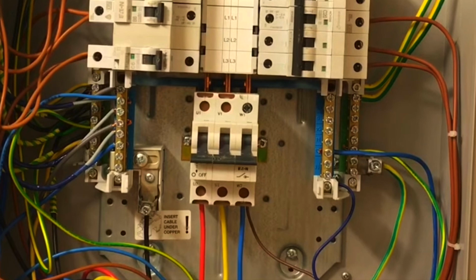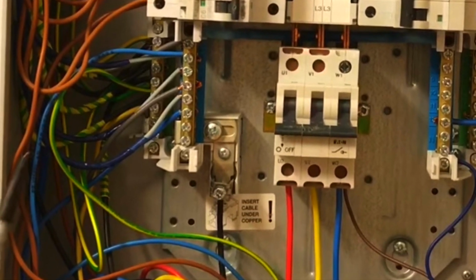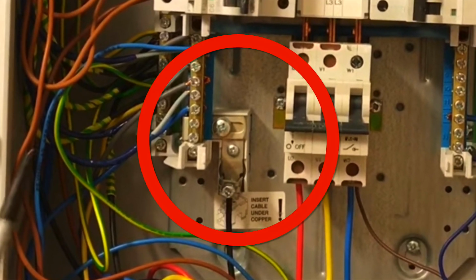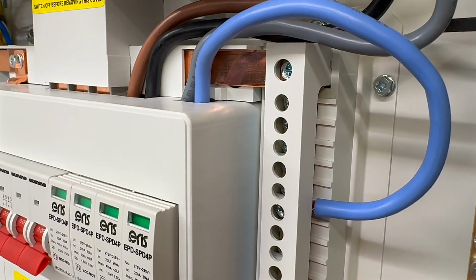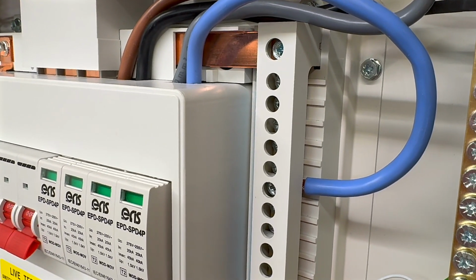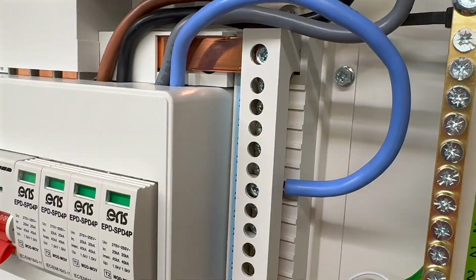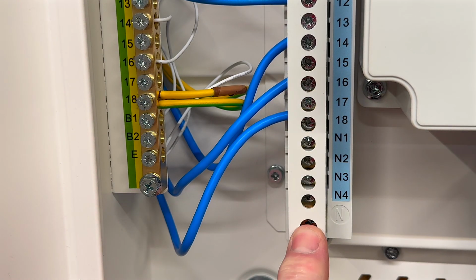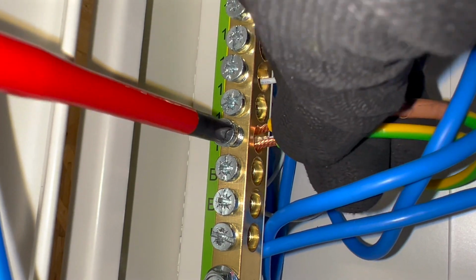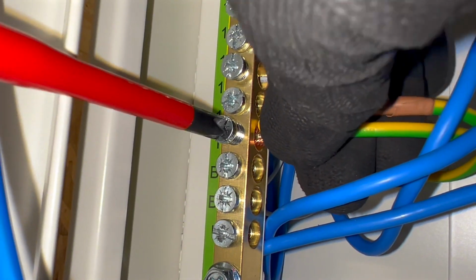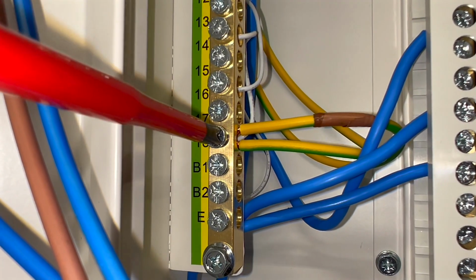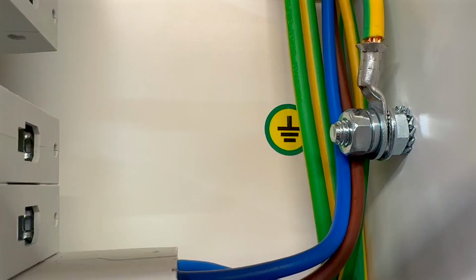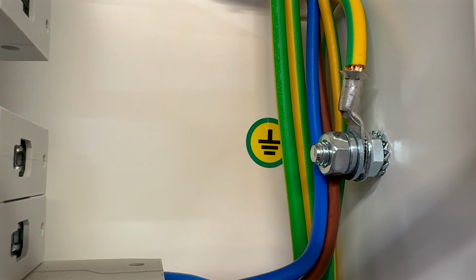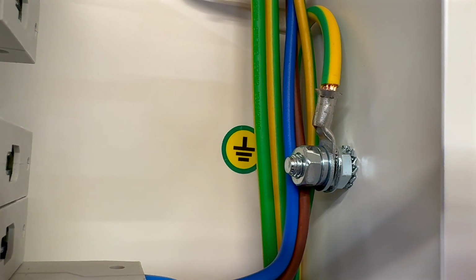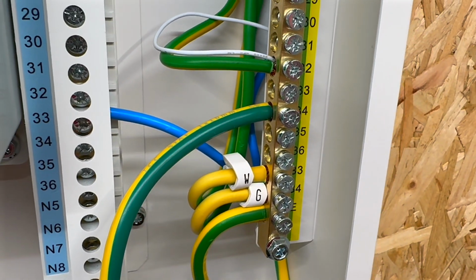In boards with a 3-pole switch, the neutral connection often includes a removable link, allowing for isolation during maintenance. The neutral bar is insulated from the metal chassis, as the neutral conductor is classified as a live conductor. The neutral bar is further designed to be touch-proof on many boards, ensuring added safety. Each side of the board also houses a brass earth bar, which connects to the circuit protective conductor. Smaller incoming supply cables are connected directly to the earth bar, while larger cross-section cables are secured using a bolt connection. These earth bars are directly bonded to the steel chassis, eliminating the need for additional interconnections.